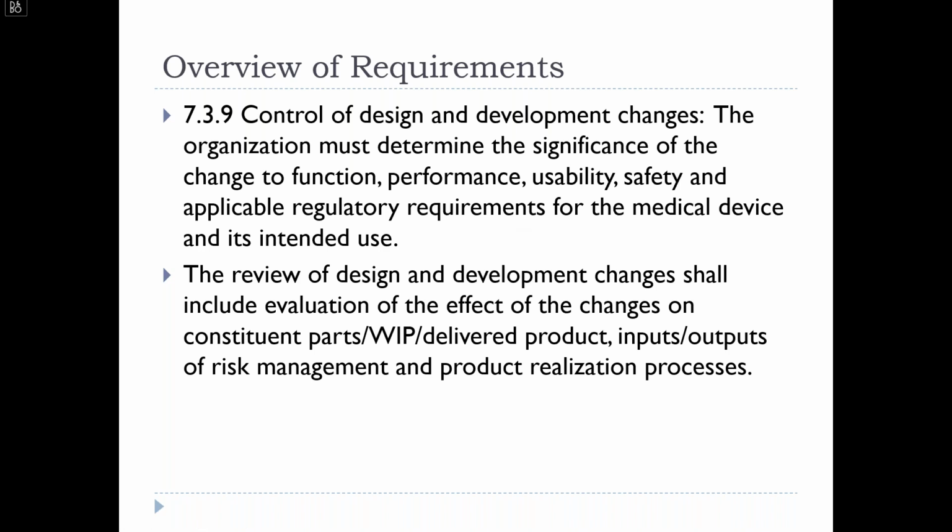And finally, 7.3.9 talks about design and development changes. The organization needs to determine the significance of any changes to the function, performance, usability, safety, and applicable regulatory requirements of the medical device and its intended use. And a review of the change shall include evaluation of the effect of the change on parts, WIP, delivered product, inputs, outputs of risk management, and product realization processes. So certainly a holistic approach.